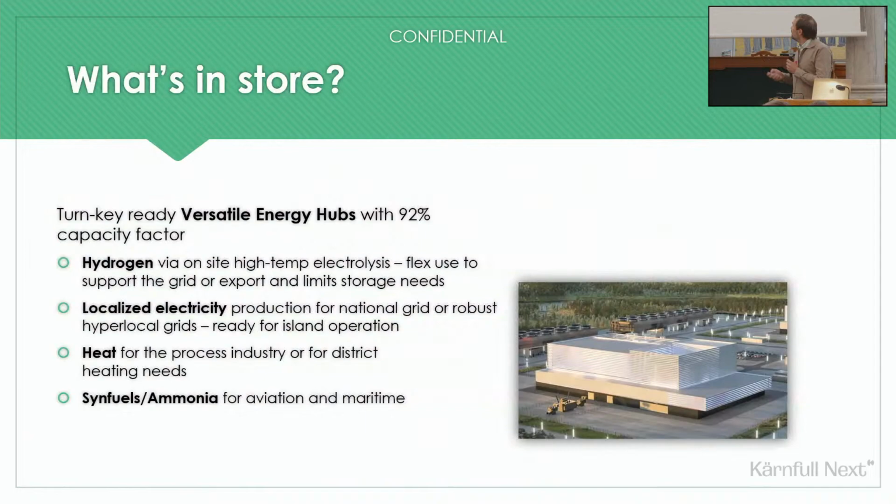We've touched on this several times before, but when we talk SMRs and developing nuclear projects, we never talk about electricity. We always talk about energy. Even though a BWRX-300 has 300 megawatts electrical, it has almost 870 megawatts thermal. Today in Sweden, that is considered waste, included in Swedish energy inefficiency, because we put it in the water for cooling. But we could take care of that instead, using that heat, superheated maybe, as Rauli mentioned, to make use of high temperature electrolyzers, or we could use it for district heating, for instance.